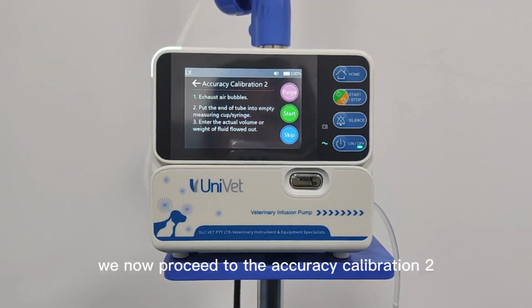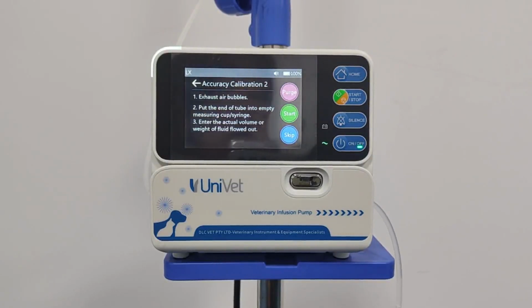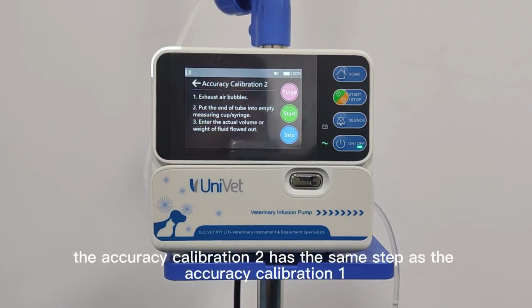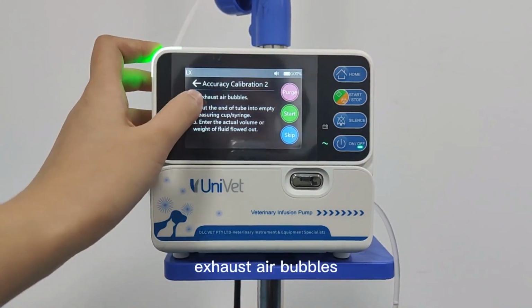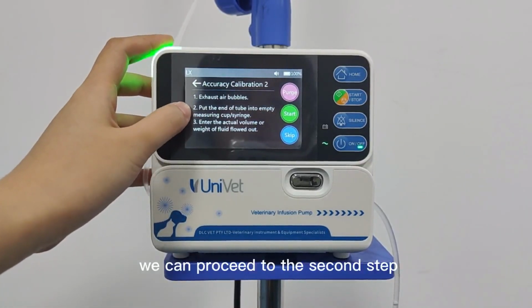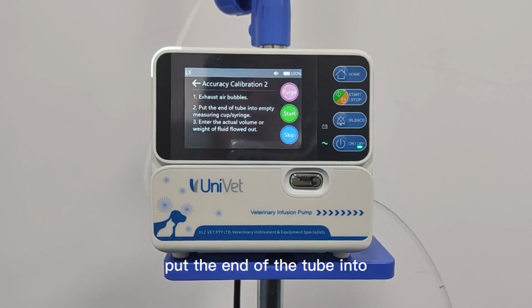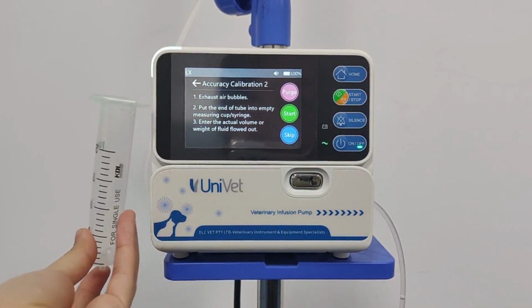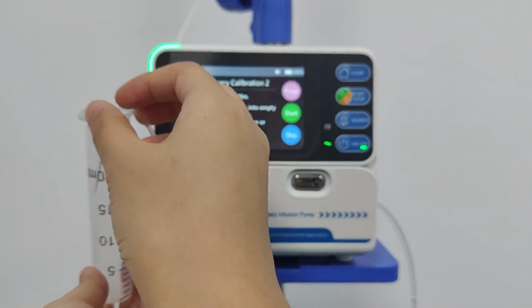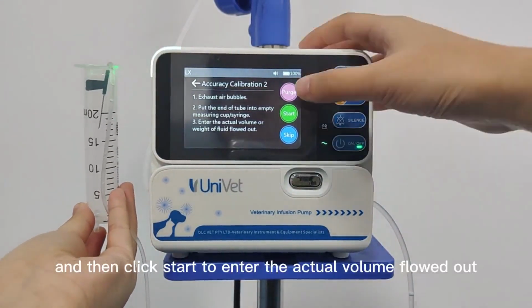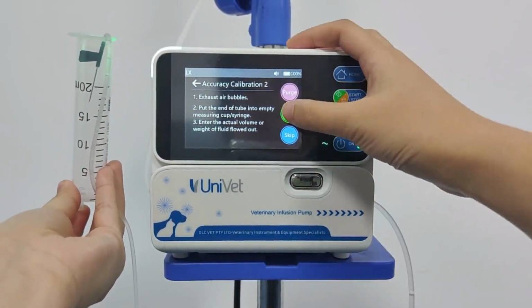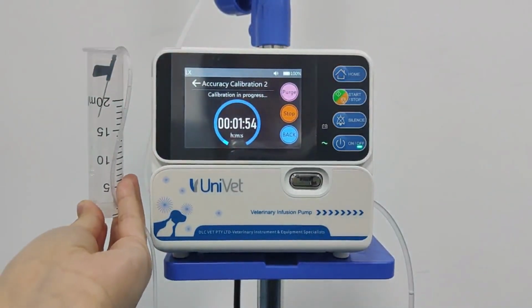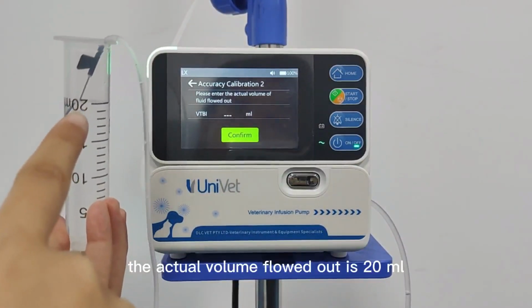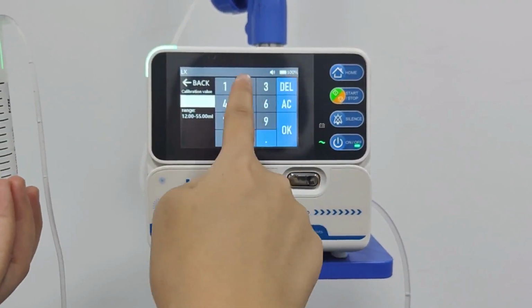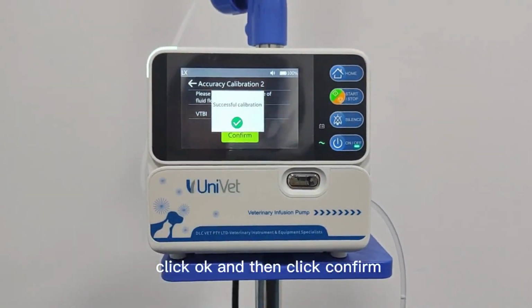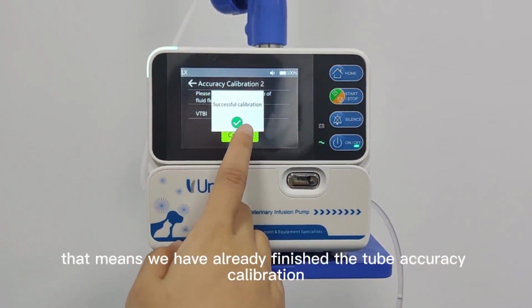We now proceed to the accuracy calibration 2. The accuracy calibration 2 has the same steps as the accuracy calibration 1. First, exhaust air bubbles. Because we have already exhausted all the air bubbles, we can proceed to the second step. Put the end of the tube into another empty syringe cup. And then click Start to enter the actual volume flow out. The actual volume flow out is 20 milliliter, so we input the VTBI, 20. Click OK, and then click Confirm. Successful calibration. That means we have already finished the tube accuracy calibration.